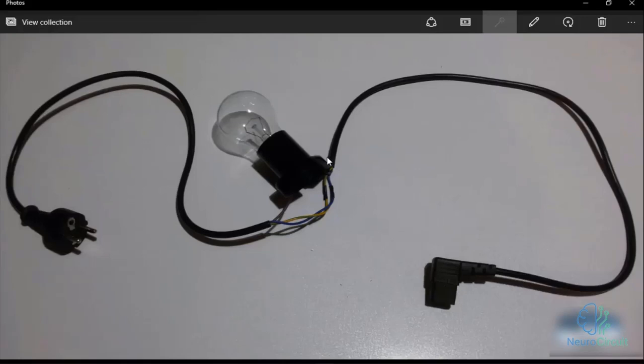If you connect a power supply to the test lamp and the lamp does not light up, it means the power supply does not have a short circuit or internal connection, and you can work with it more easily. The purpose of the test lamp is to prevent a power supply with an internal short from developing further problems, or for the circuit breaker to trip completely so we can work safely.